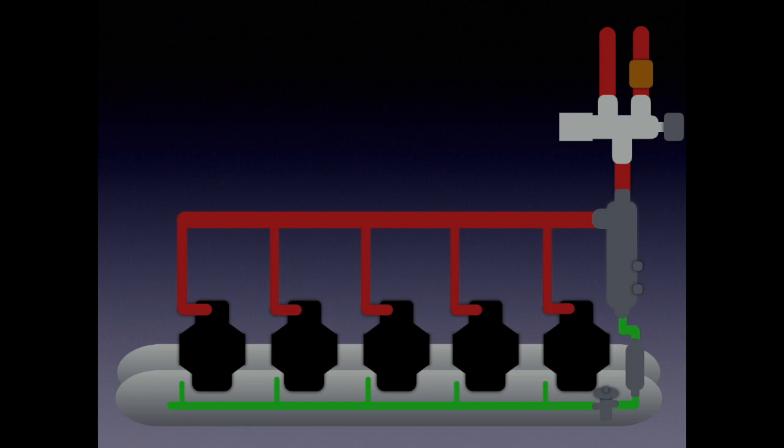Typically, I don't know, 20 to 30 pounds over suction. This is pumping that oil. This pumps that oil into floats that are attached to the compressor. These floats house enough oil to be pumped into the compressor to keep them going. Additionally, out of these floats we have what we call an oil equalizing line. Now an equalizing line allows each compressor to have the optimal amount of oil. So we're not favoring one compressor over the other. They're all getting the same amount of oil as long as oil is there to give.